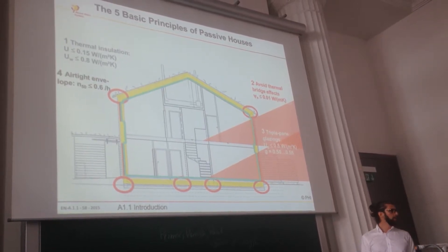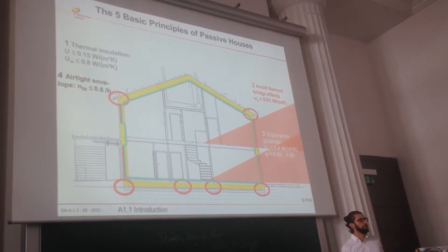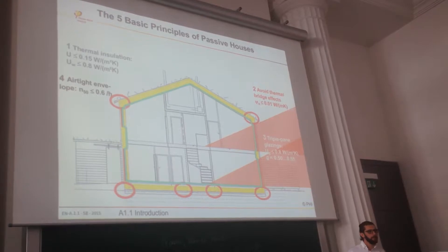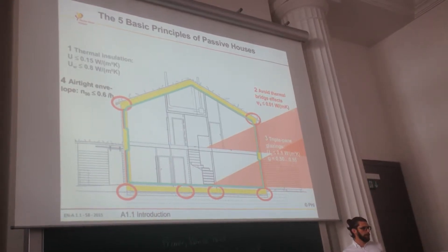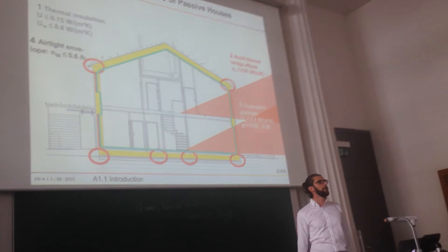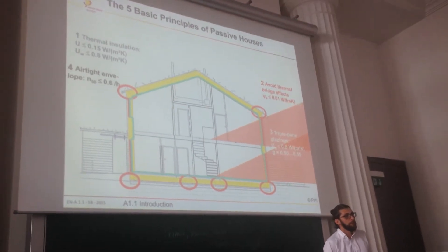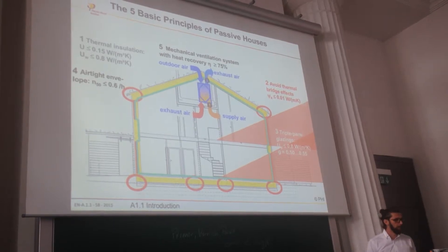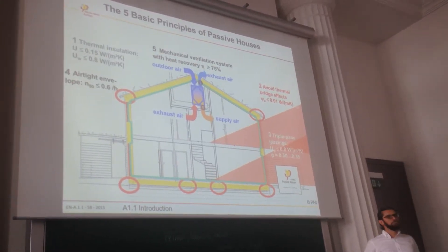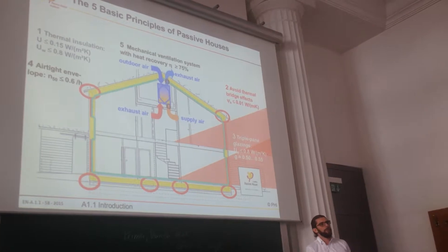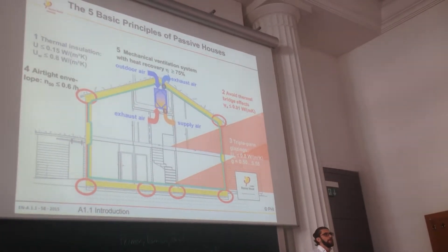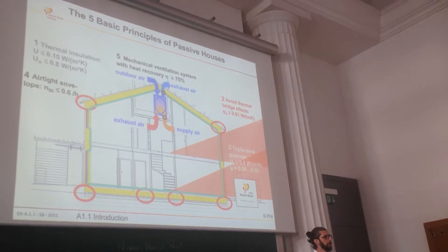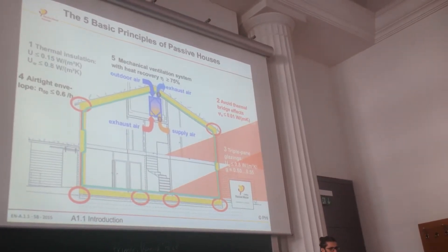Air tightness is measured in the N50 value, which should be below 0.6. In Austria it's below 1 — that will be 1 if you are using ventilation units, to make the ventilation units more efficient. And the ventilation units — you have to optimize and measure them. The heat recovery should be higher than 75%, and the energy demand should not be too high.